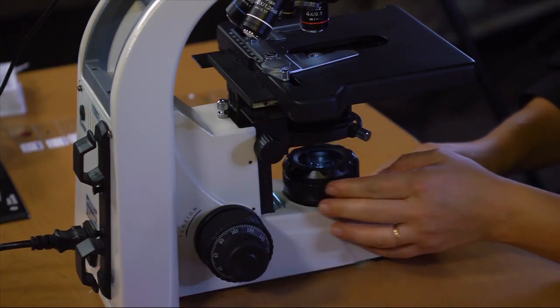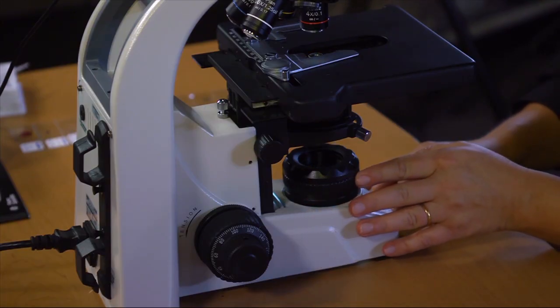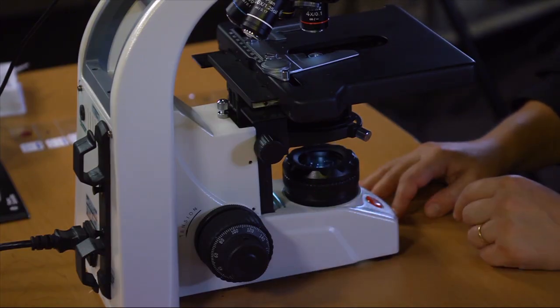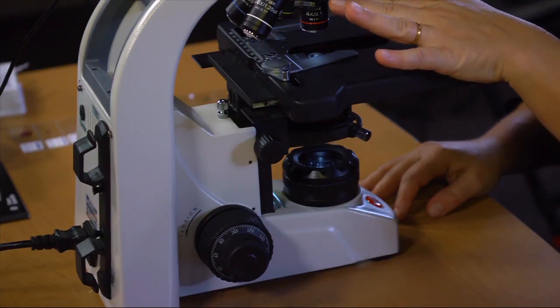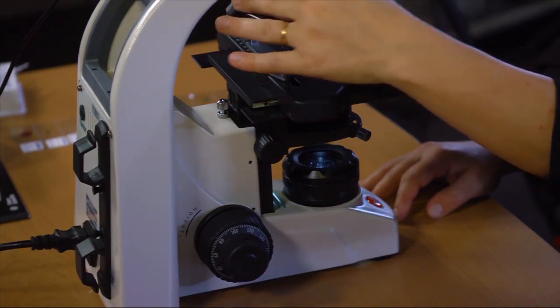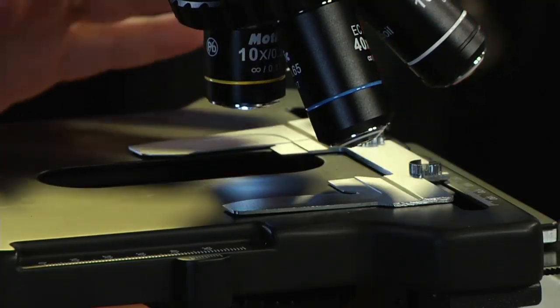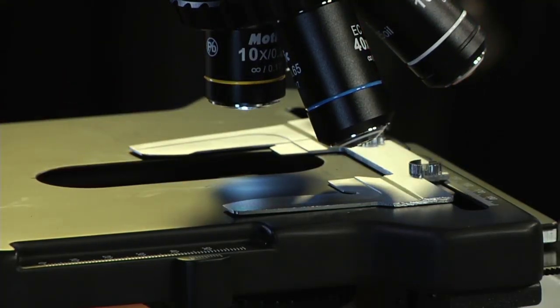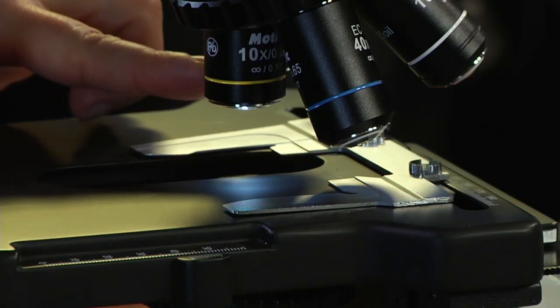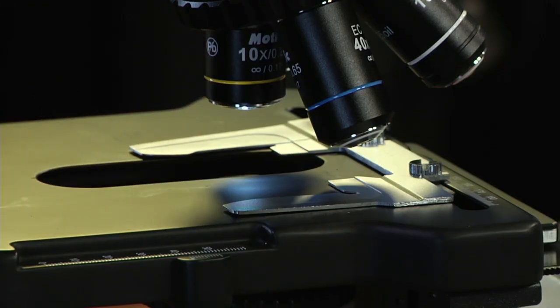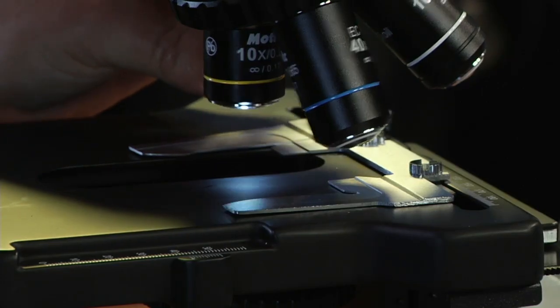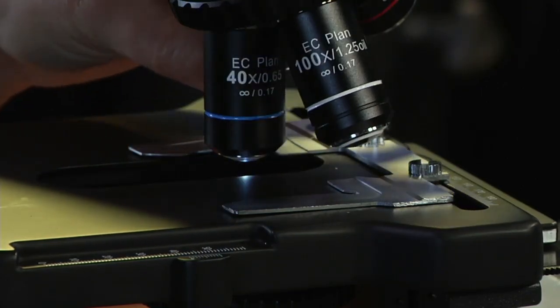Down here at the bottom is your field diaphragm, and that has to be closed and then later opened during the Köhler process. The last part we talk about is our lenses. You can see that each of the lenses has a number on it. This is the magnification of the lens. You also have a 10-fold magnification in your eyepiece. So on this yellow lens, it is a 10x magnification. The eyepiece also is 10x, so the total magnification using this lens is 100x. On this microscope we have a 4, 10, 40 and 100x lens.